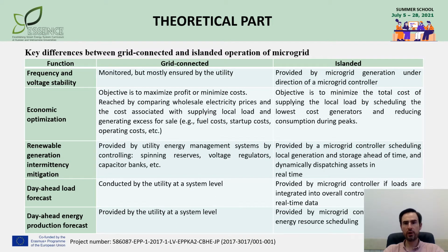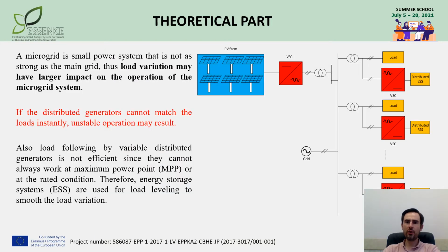In case of islanded operation, there is a need for proper planning of microgrid capacities and forecast of renewables to decide on the required size of reserves. So it's clear that grid-connected operation has many benefits for the grid, and it's preferable to consider it as the normal operation mode for a microgrid. The islanded operation of a microgrid is complicated due to the comparable size of loads and generating sources. Thus, normal load variation causes much larger imbalances in a microgrid than in a utility grid, and thus puts additional requirements on the distributed generation control.